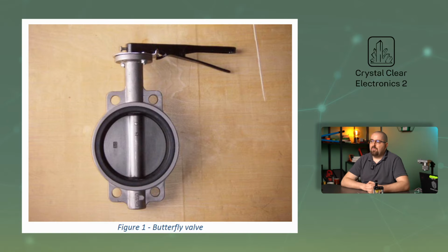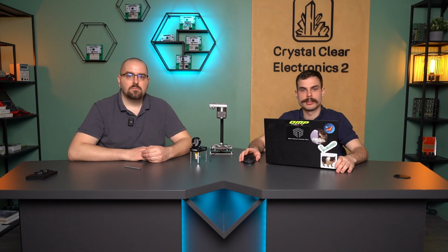Perhaps one of the simplest designs is the so-called butterfly valve. A manually operated version is shown in this picture. It's basically made of a tube and a circular plate on a rotating shaft, which blocks the fluid from flowing through, thereby increasing the hydraulic resistance and reducing the amount of fluid flowing through the valve in a unit of time. The butterfly valve's hydraulic resistance is small, and a small torque is required to move it, but it can only be used at low pressures.